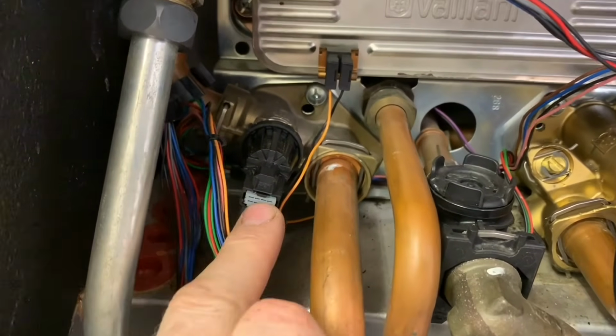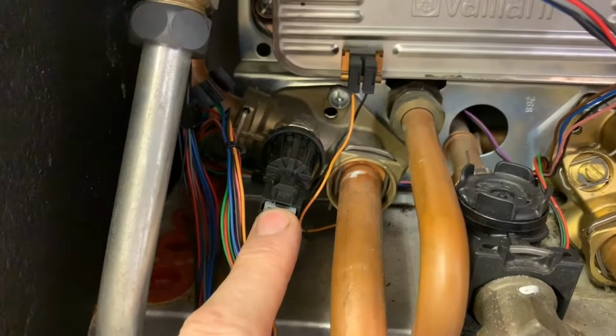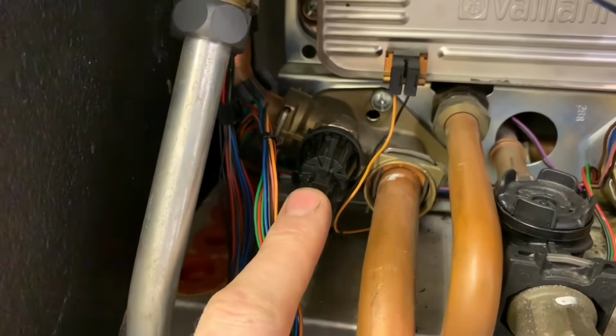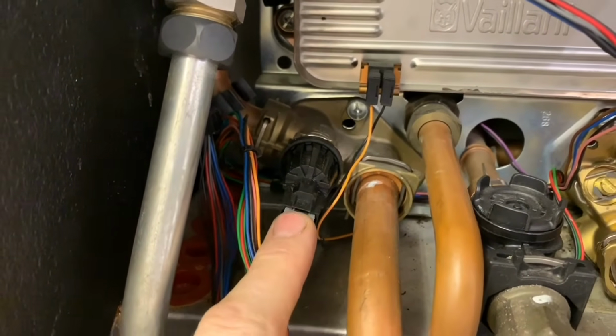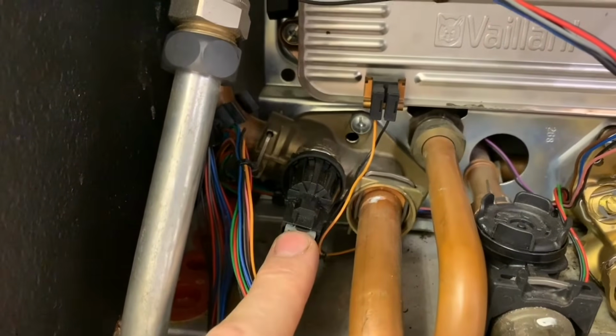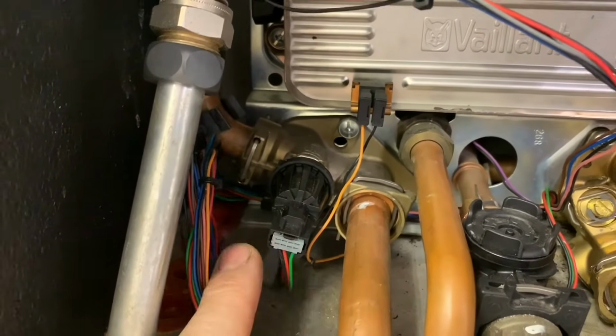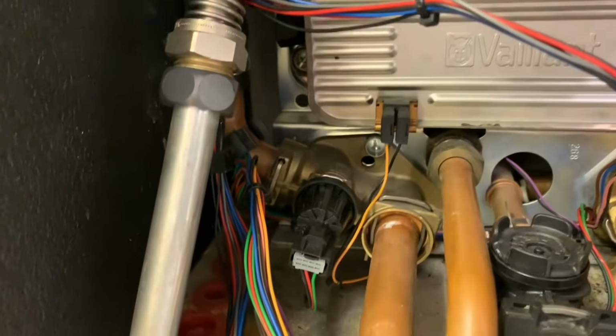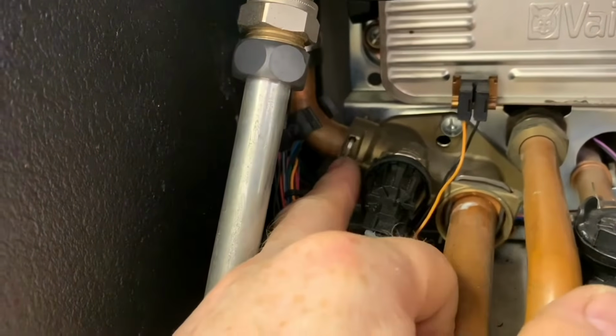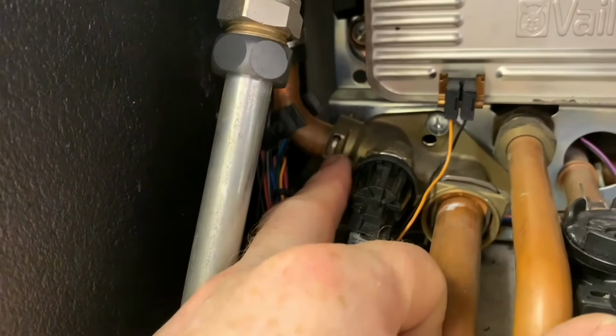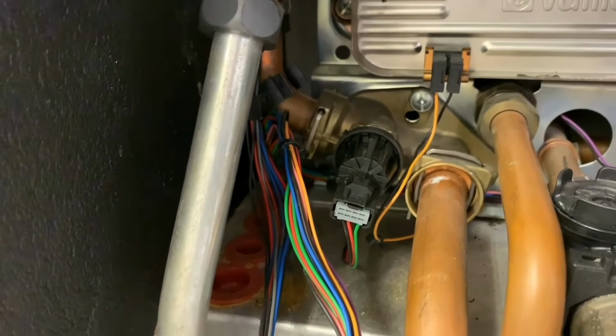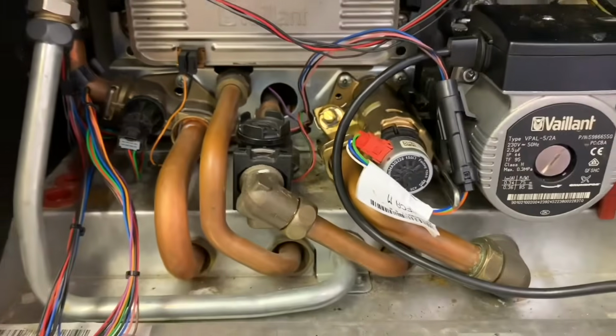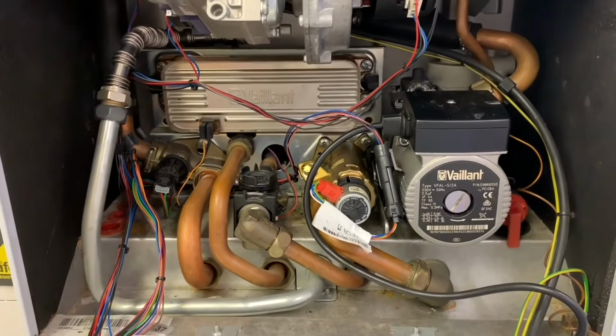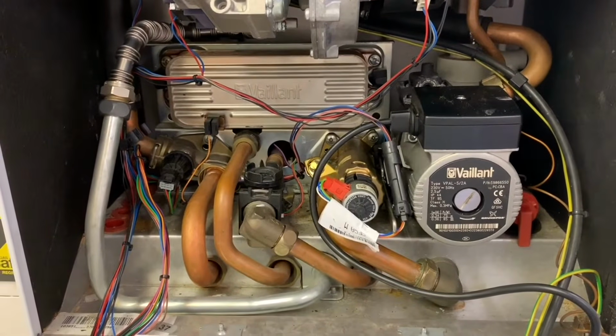The thing we've got here now is the troublesome low water pressure sensor. Again, when we have a look at this a bit more closely, I'll explain more about this. But this now has actually been moved from this position because it has been troublesome, up into the top around here. But again, once we get this burner out, we'll have a look at that. Also, what's inside here, again, when we strip it, we'll see it. There's a filter which can also be troublesome. So that's the water set to the hydro block down at the bottom.